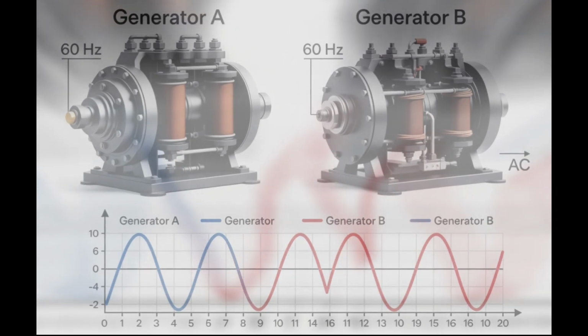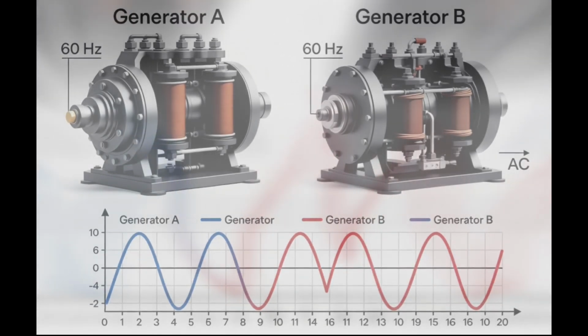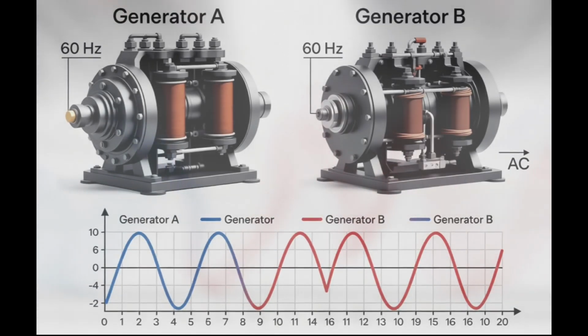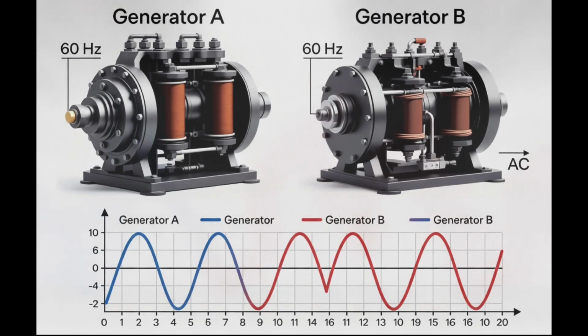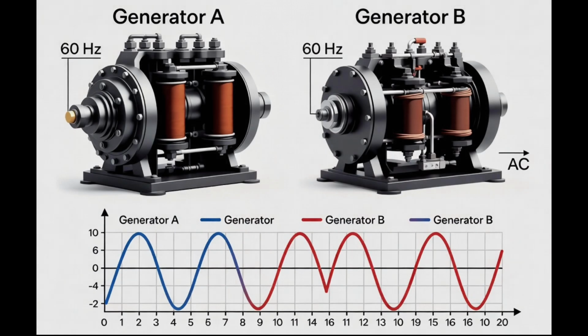Both the eastern and western grids operate on a strict frequency of 60 Hz, but they are not synchronized. Imagine 2 massive gears spinning at the exact same speed, but the teeth of the gears are slightly out of alignment. If you try to smash them together, they will shatter. If you build a standard, high-voltage AC transmission line and connect the eastern grid directly to the western grid, the out-of-phase power would collide violently, triggering catastrophic fault currents, instantly blowing out circuit breakers, detonating power transformers, and cascading into a blackout that could take down multiple states.